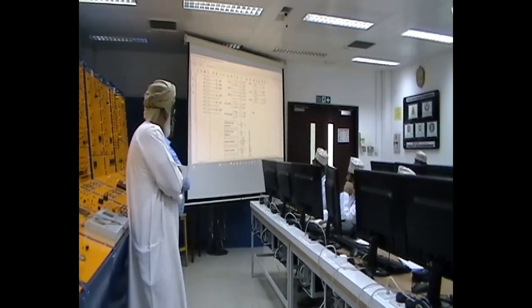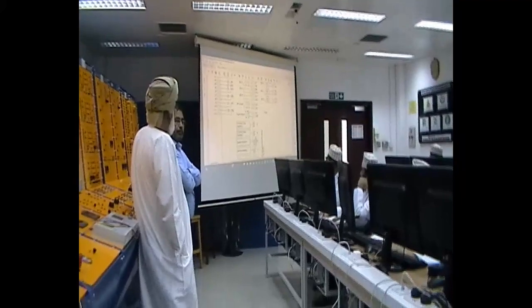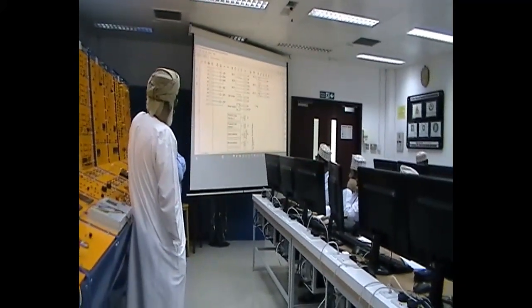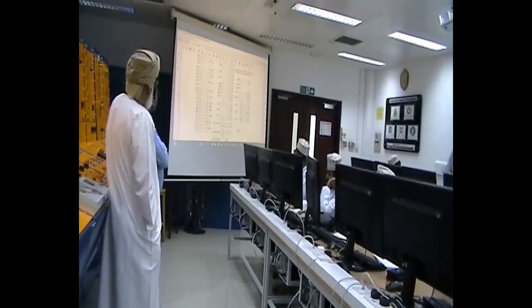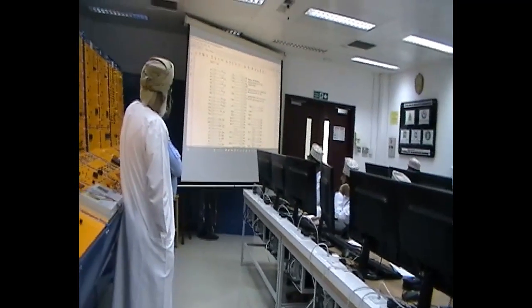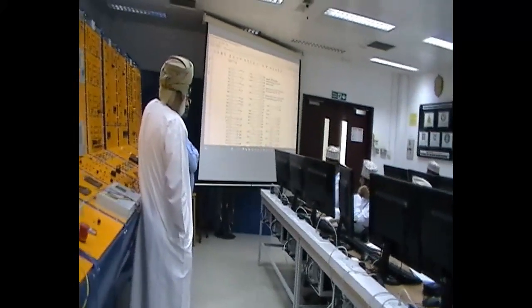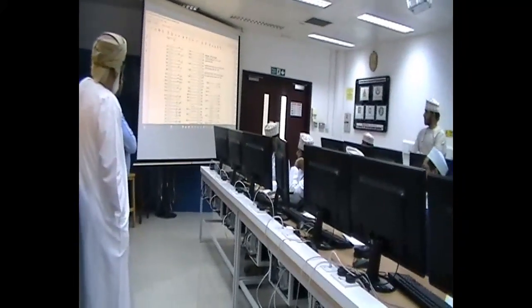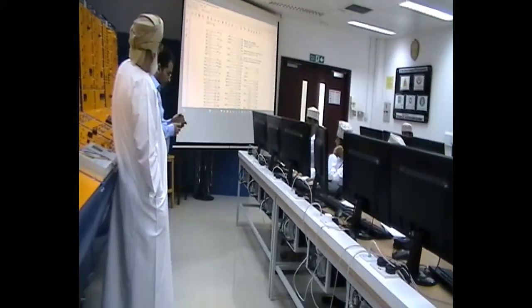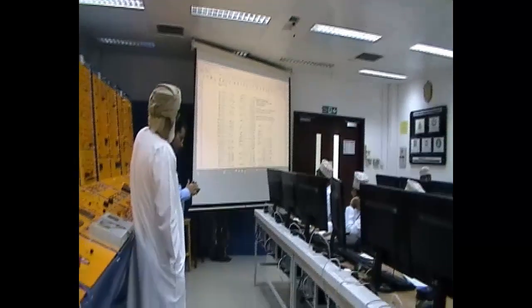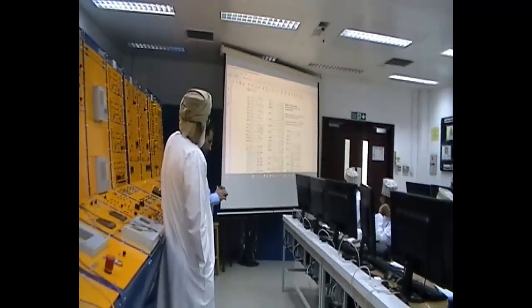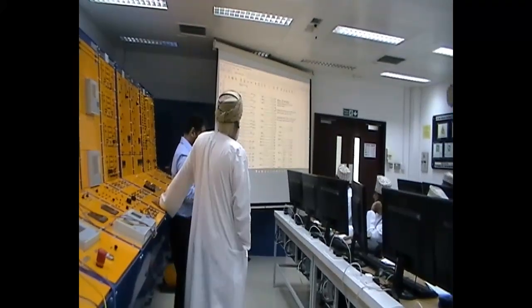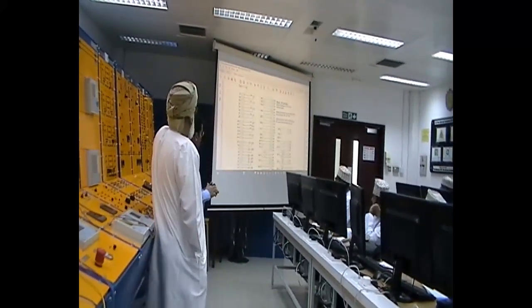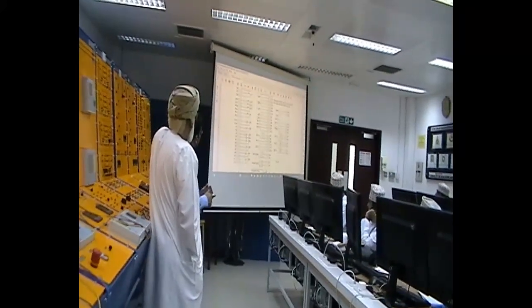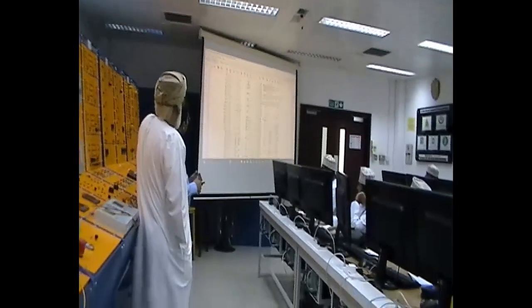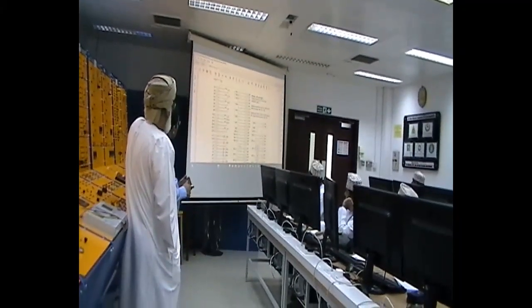The auxiliary supply of the relay is in the K card, and it's 110 volt DC, and nowadays relays accept AC also. Input and output: I can configure any one of the binary outputs to the trip, to the start, or whatever signal I want from the relay. So we've connected binary output 4 to the, I presume, no, sorry, it was 4 and 5 basically, but we can open it from the configuration of the relay. 4 and 5, we'll check it from the relay.